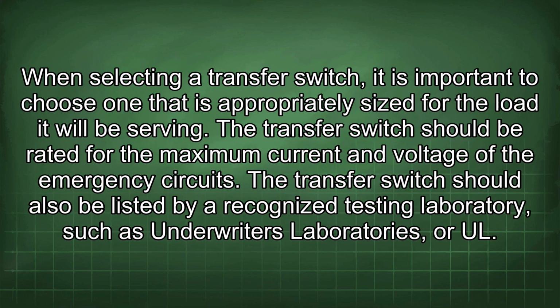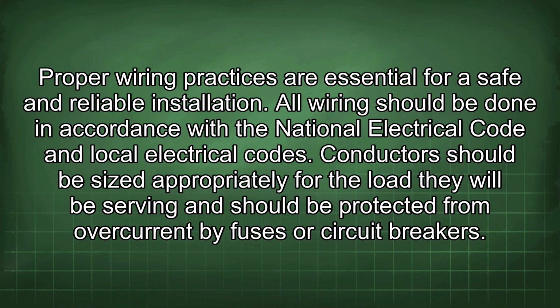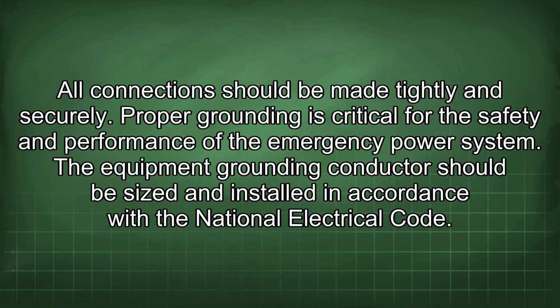When selecting a transfer switch, it is important to choose one that is appropriately sized for the load it will be serving. The transfer switch should be rated for the maximum current and voltage of the emergency circuits. The transfer switch should also be listed by a recognized testing laboratory, such as Underwriters Laboratories, or UL. Proper wiring practices are essential for safe and reliable installation. All wiring should be done in accordance with the National Electrical Code and local electrical codes. Conductors should be sized appropriately for the load they will be serving and should be protected from overcurrent by fuses or circuit breakers. All connections should be made tightly and securely.